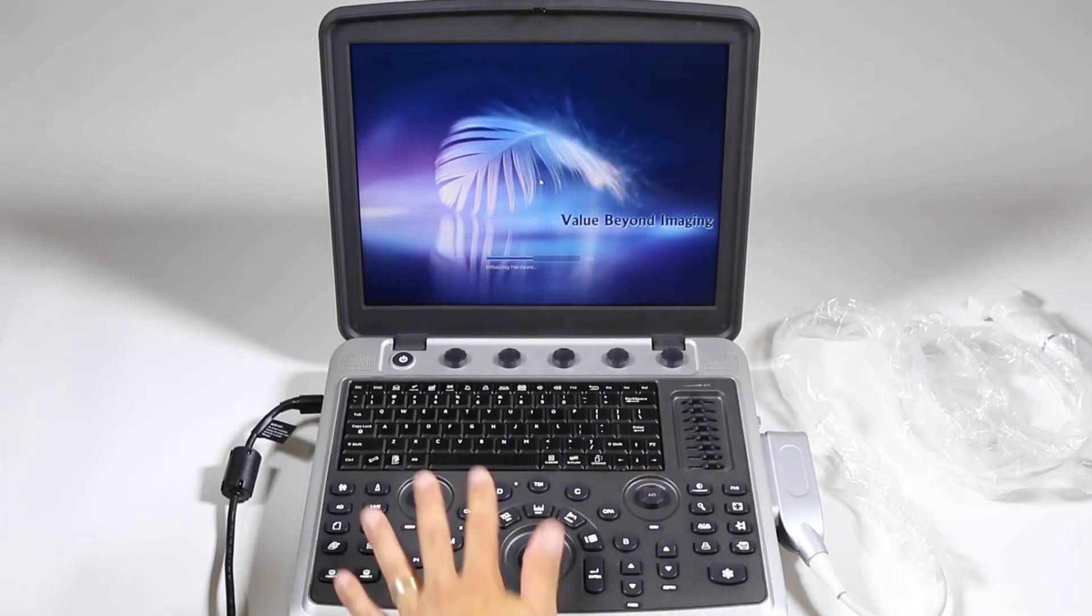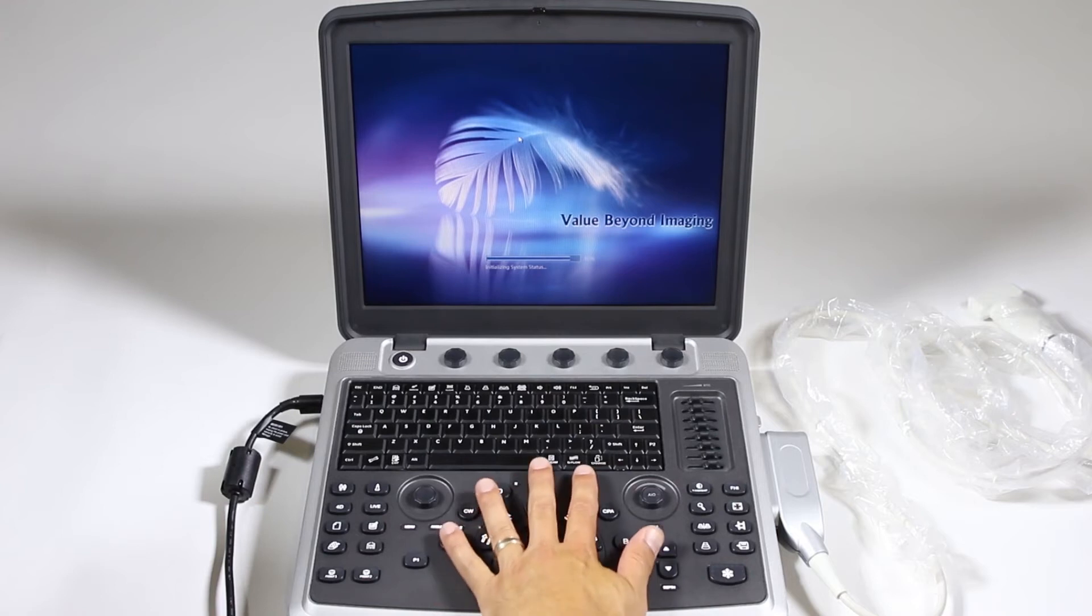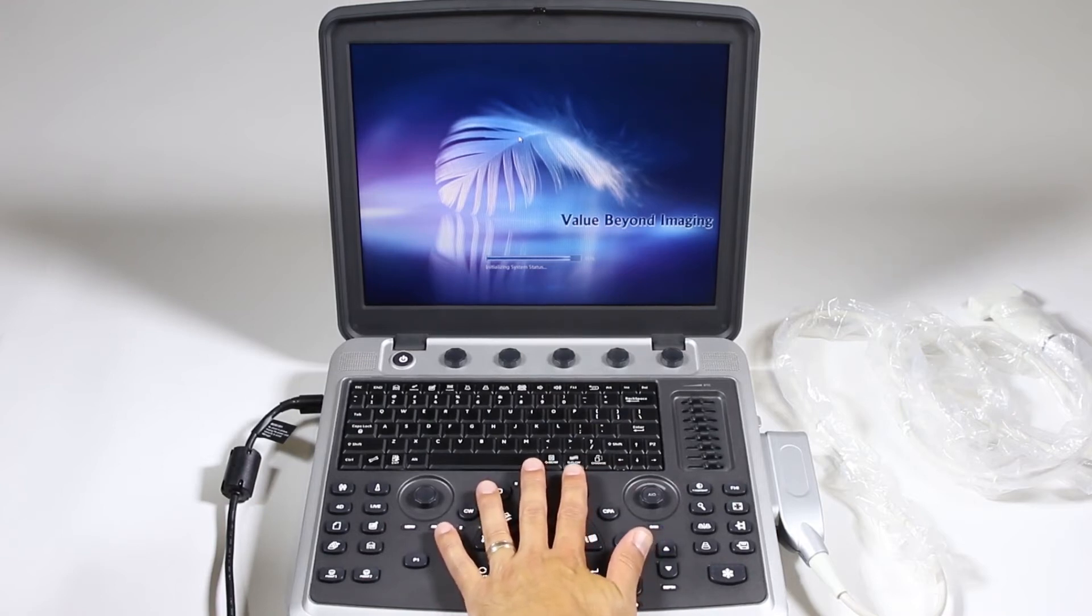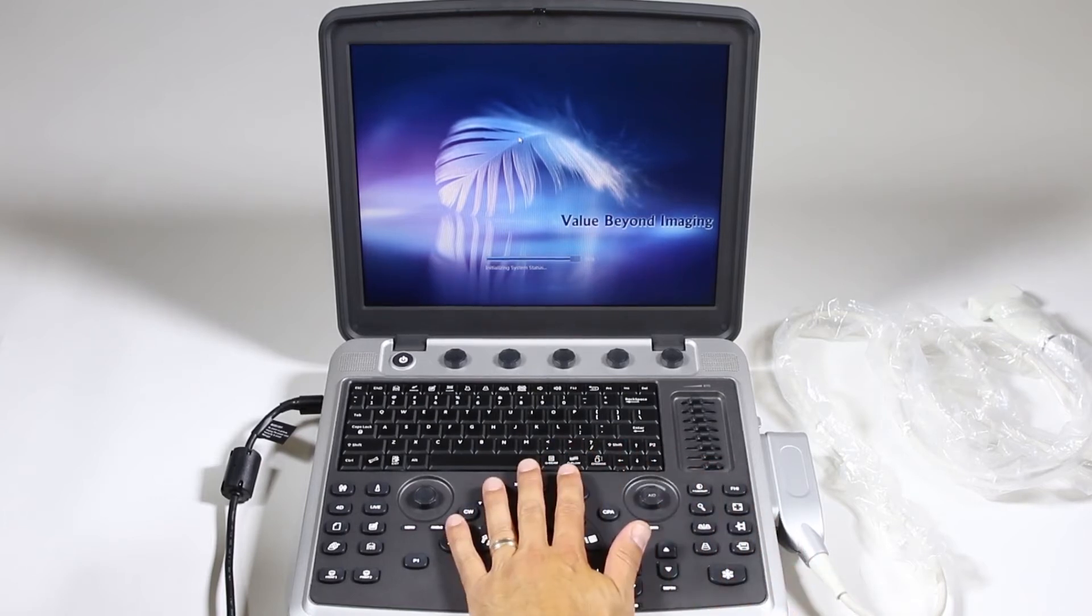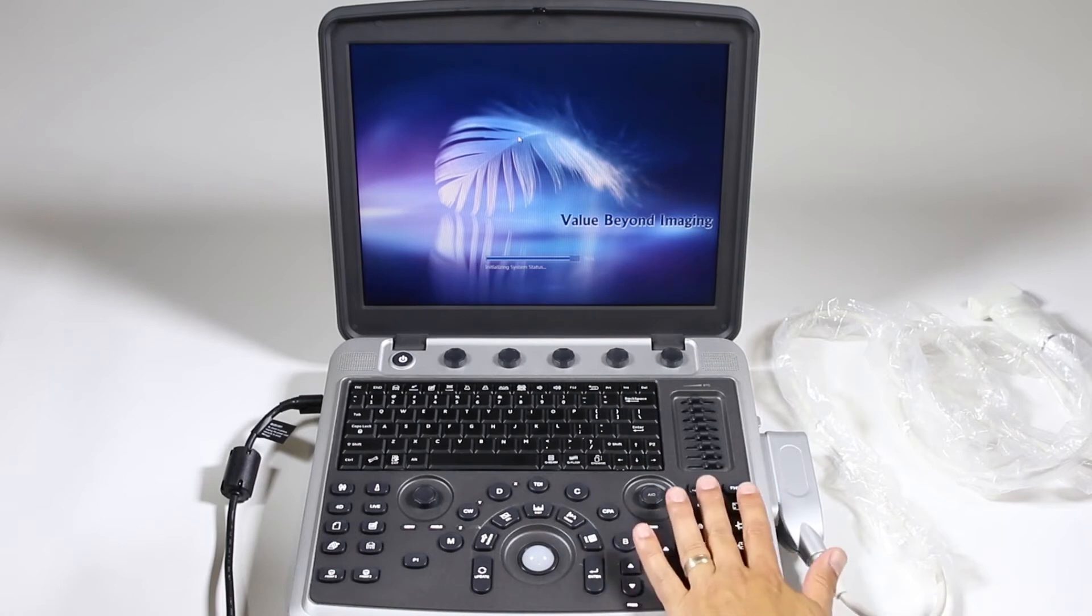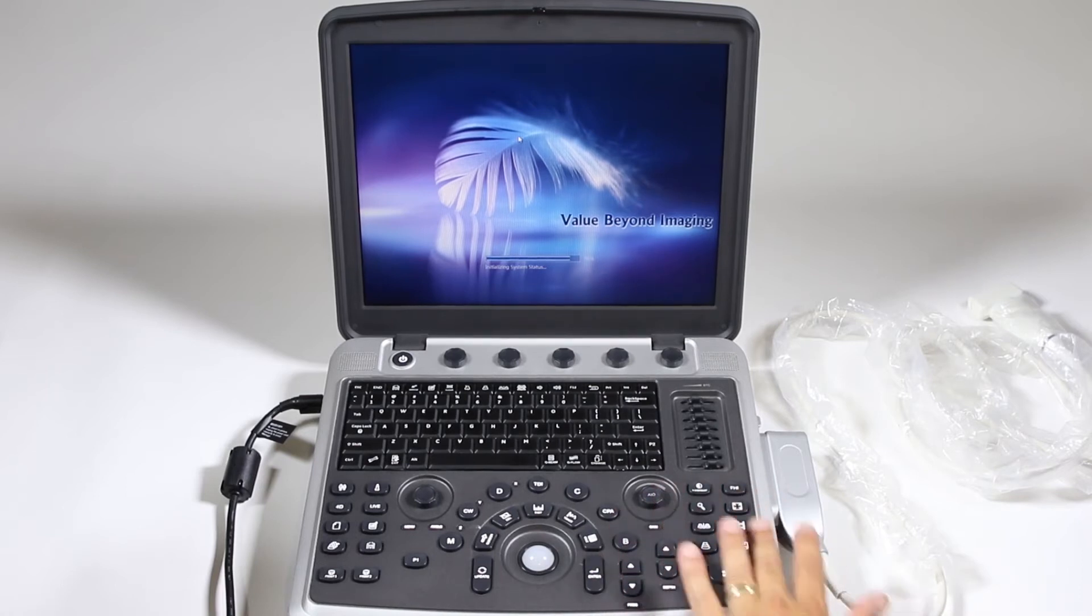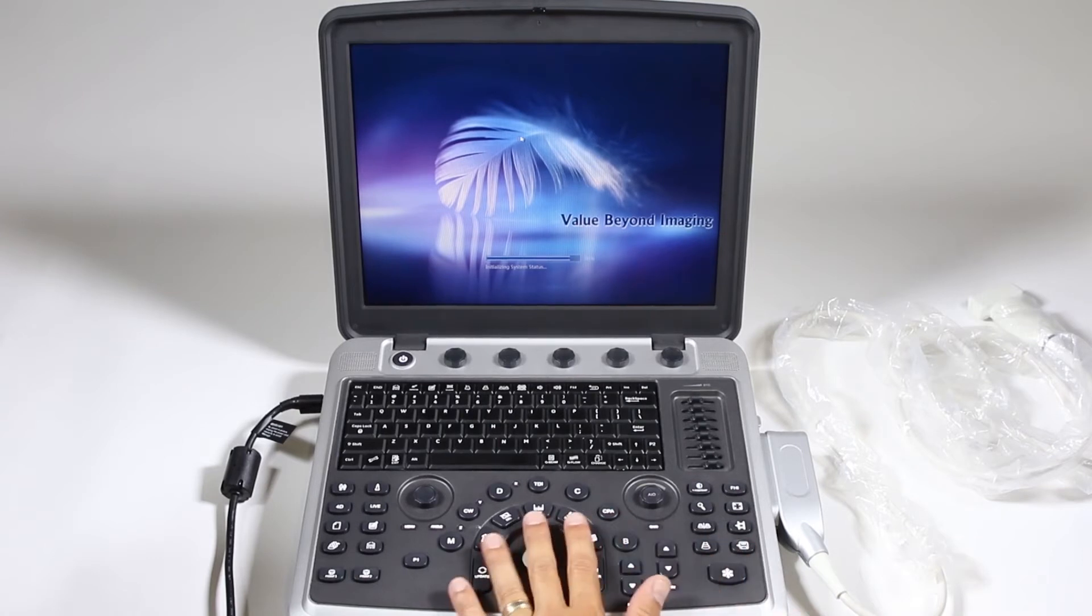The whole keyboard and user interface is really designed around your hand. The most used functions during an exam, they'll try and put right in this area or closer to where you would be scanning. Like if your hand's away on the patient, it'll make things nice and convenient right here for saving and zooming, adjusting the gain, the depth, and the frequency.